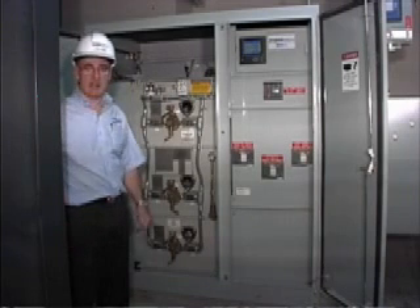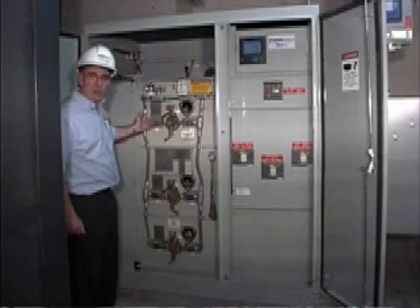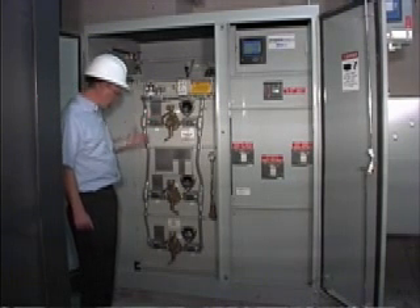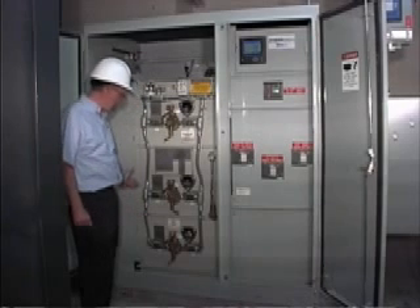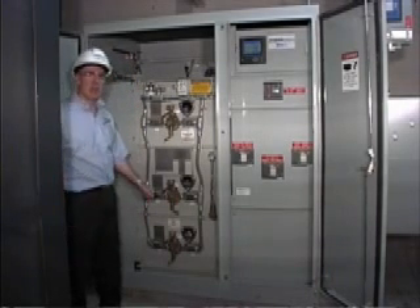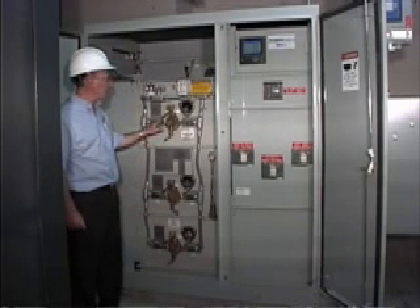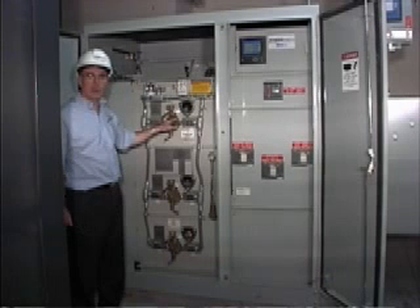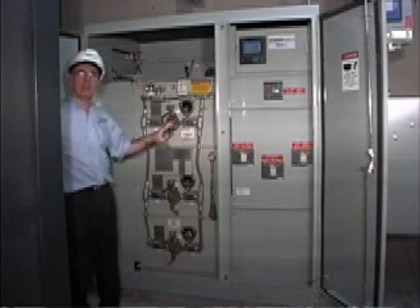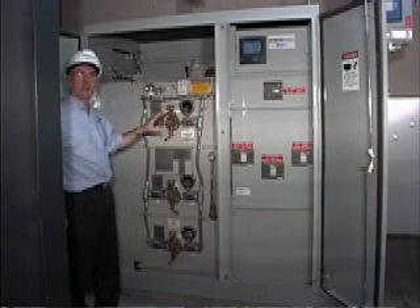This particular unit is in service now, and it is a loop switch arrangement. So we have two switches for the loop, one coming in here and one coming in here, and a separate switch for the transformer. Each of these switches is rated a full 600 amps load break, and this one has been ordered with the ground, open, and closed positions. The ground position being integral to the switch, so you can go to ground by simply operating the switch from open to ground.